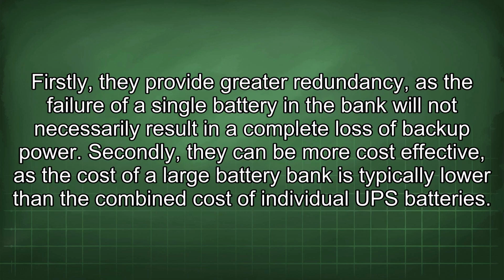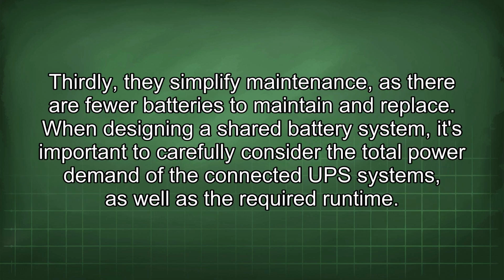Firstly, they provide greater redundancy, as the failure of a single battery in the bank will not necessarily result in a complete loss of backup power. Secondly, they can be more cost-effective, as the cost of a large battery bank is typically lower than the combined cost of individual UPS batteries. Thirdly, they simplify maintenance, as there are fewer batteries to maintain and replace.